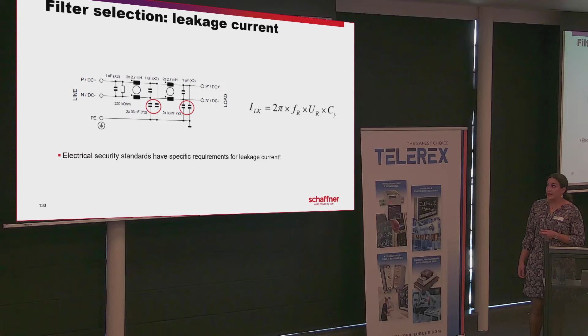So how do we get a balance between the leakage current that we should keep very low and the high value of the common mode capacitor that we should insert within the filter? That leads us to a specific application that has very specific requirements. It's actually the medical standard. If you have ever faced a medical standard, we all know that it has a very severe requirement when it comes to leakage current. So we are simply not allowed to put any common mode capacitors within the filters.